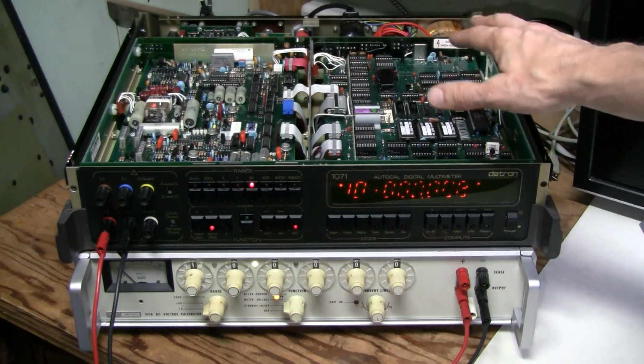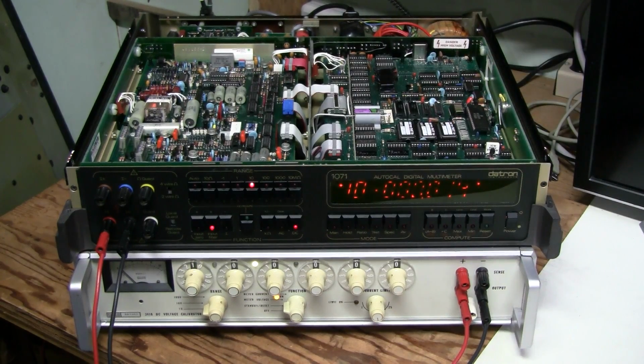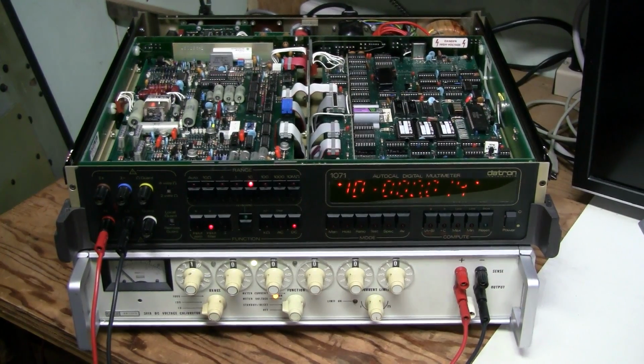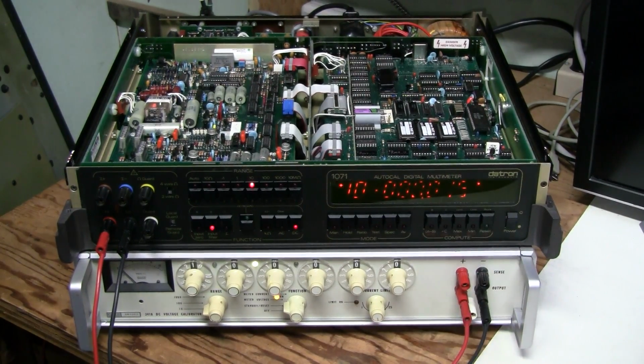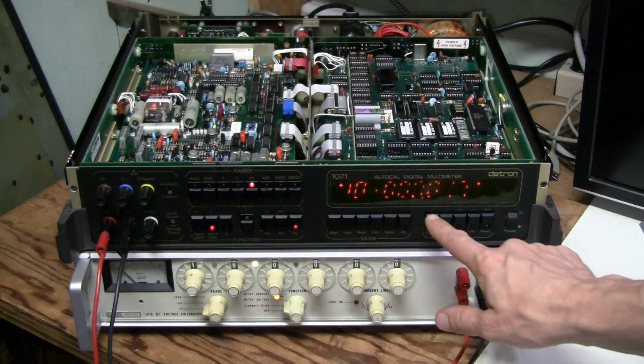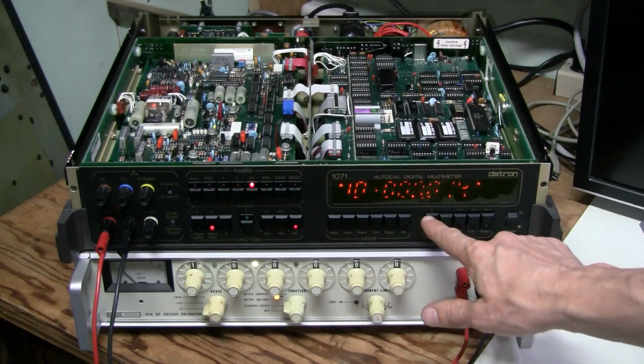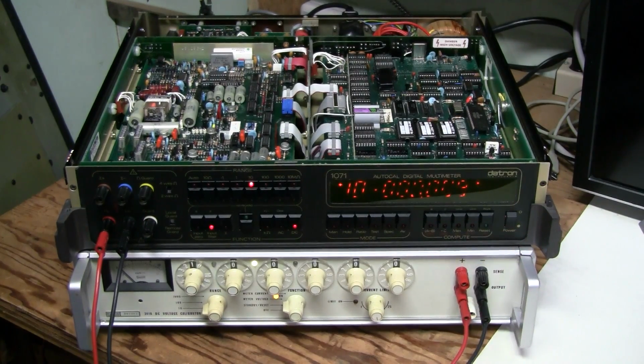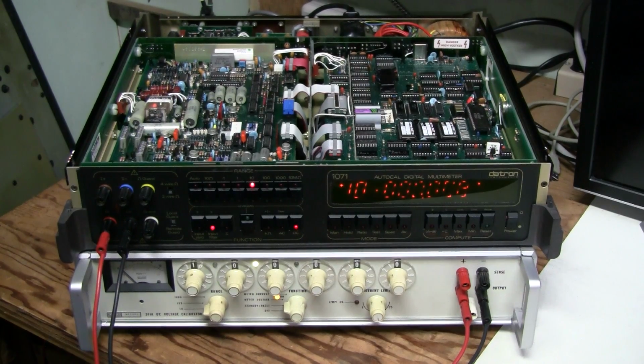So after reseating the socketed chips, that problem with unresponsive controls and locking up went away, and I have never seen it again. Then I started desoldering this faulty switch, and in the process the switch started working. So now it is clicking and working just fine, no problem anymore. Then I started studying the service manual, which is very good, with full schematics, description of operation, adjustment procedures and such. So I found that the fail message was about the corrupt calibration parameters. So I didn't really need to worry about these memory chips, because calibration parameters are lost anyway.